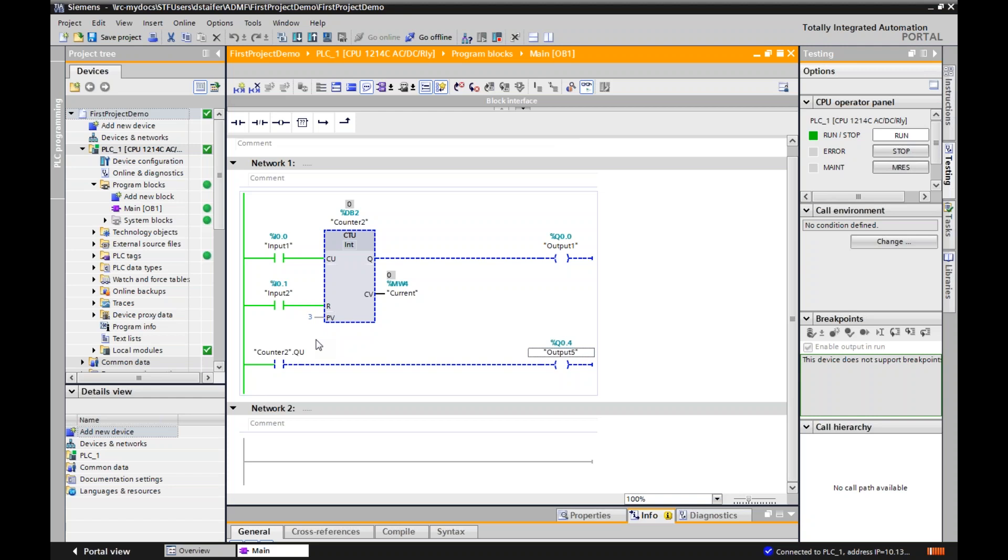If I want to reset it, I can even reset it with this output on because the reset is dominant over the counter up. And right now, since I haven't changed the state of my counter input, it's not counting while it's on. You would think, well this is true, it's going to count up. No. It's got to recognize that it goes false first before it will count again when it goes true. So keep that in mind. If your counter isn't counting, it could be because your reset is still on, or you haven't changed the states of the input conditions in some way.